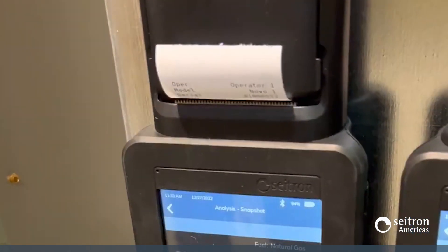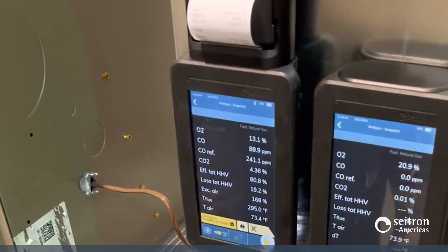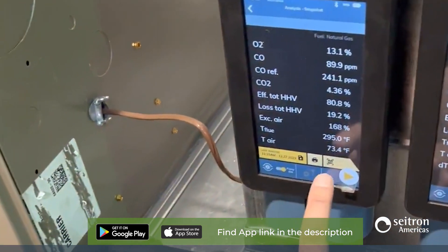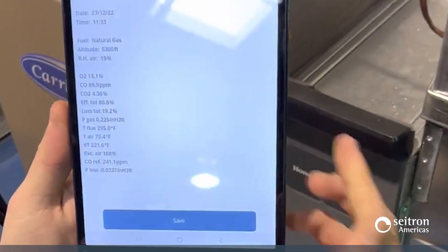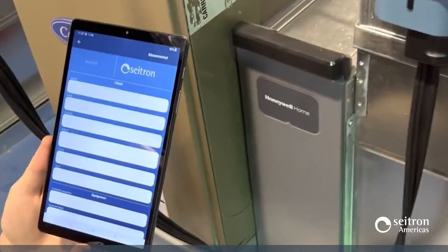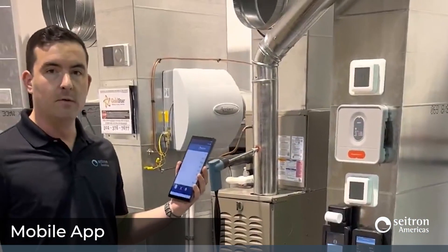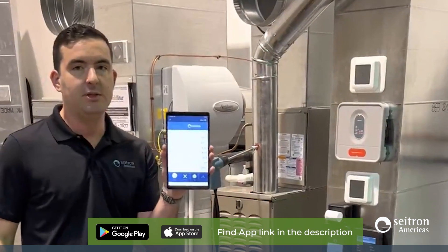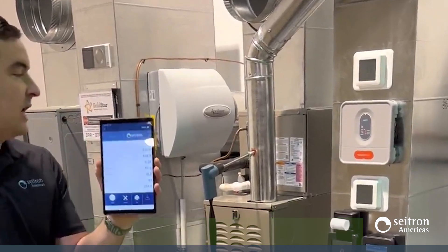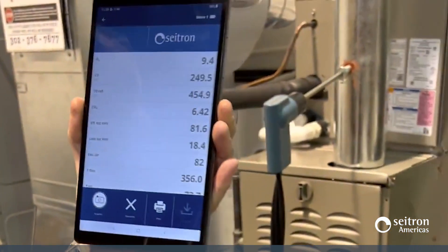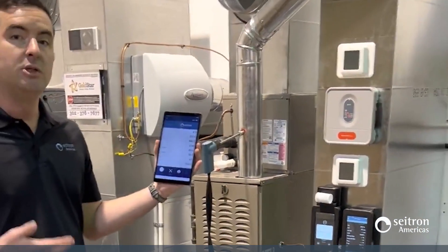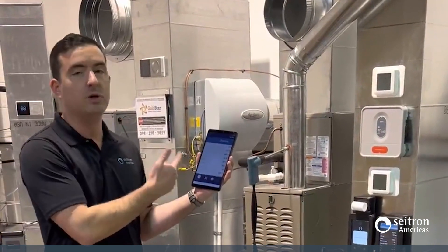If you prefer to generate a digital report, you can download the free Seitron Smart Analysis mobile app. Using any Android or iOS device, you can generate a QR code based off of the combustion analysis, scan that QR code, and bring the readings back into your device. From there, you can save the data, enter in the customer's information, equipment details — make, model, serial number — as well as your own information, and then email out a PDF or Excel report from the field. Another nice feature is the ability to remotely view your readings from your phone or tablet, which is particularly useful for larger commercial systems where you might be standing far away from the measuring point making burner adjustments — no hose extension needed.